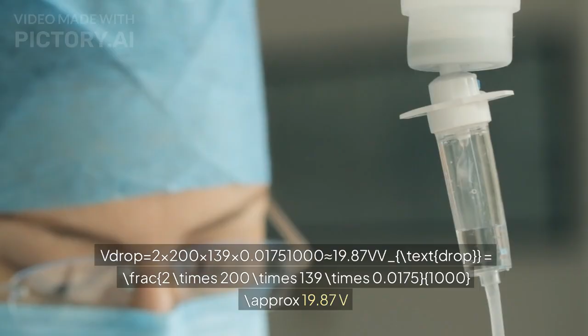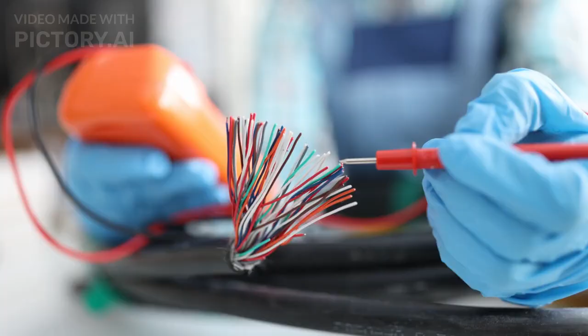3. Check allowable voltage drop. Allowable voltage drop = 415 × 0.05 = 20.75 V. Since the calculated voltage drop, 19.87 V, is within the allowable limit, 20.75 V, the cable size is acceptable.